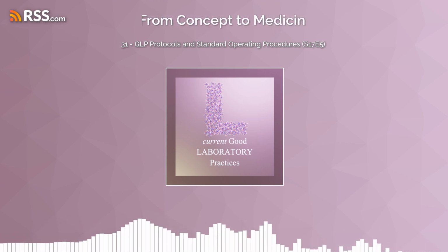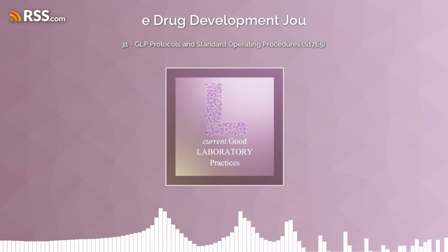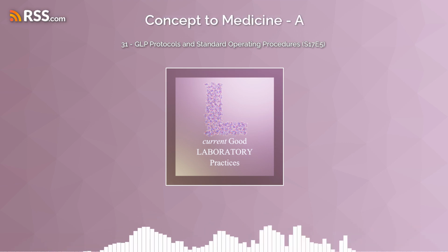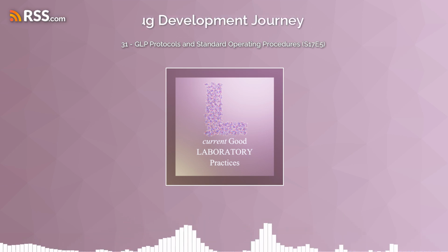It makes sense to have all those checks in place, especially when you consider how sensitive some of this lab equipment can be. Even something as seemingly small as a change in room temperature could potentially mess with the results. Oh, absolutely. Even something as simple as moving a piece of equipment to a different spot in the lab could affect how it performs. Maybe it ends up closer to a vent or in a spot with more vibrations. It can be that sensitive. That's why they often have to requalify equipment after any major repairs, if they've changed the equipment's configuration significantly, or if they've had to move it to a new location. And all this qualification work needs to be meticulously documented in, you guessed it, qualification protocols and reports.